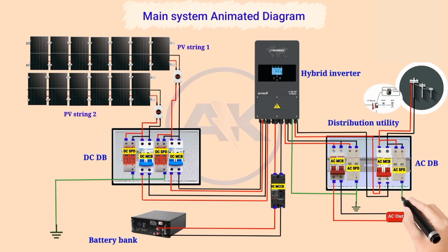our CT sensor. Important things for the CT sensor, battery communication cable and battery temperature sensor installation: please refer to the user manual. If you don't have net metering provided by your power company, make sure the arrow of the CT sensor is pointing towards the inverter.